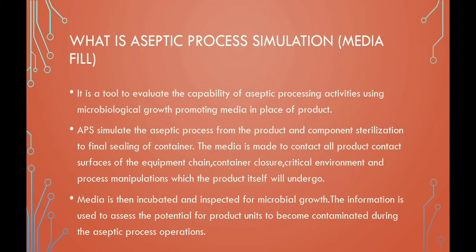The media is made to contact all product-contact surfaces of the equipment chain, container closure, critical environment, and process manipulations which the product itself will undergo. This processed media is then incubated and inspected for microbiological growth, and this information is used to assess the potential for product units to become contaminated during aseptic processing operations.